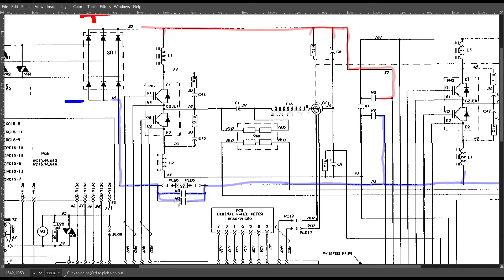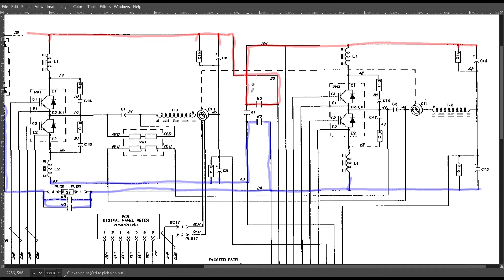Then there's a contactor here, W2, and W3, which is probably the pre-charge - I'm not certain, I've never seen this unit. It feeds the bottom part of the right IGBT module. If you're hooked up to 230 volts, then W2 closes - these two contacts close - so you end up with positive voltage at the top of both IGBT modules and negative voltage at the bottom, working in parallel. If instead you're hooked up to 460 volts, then this is what you get.